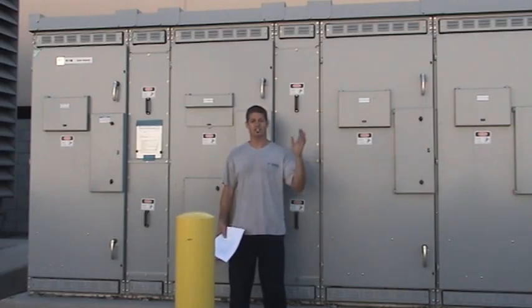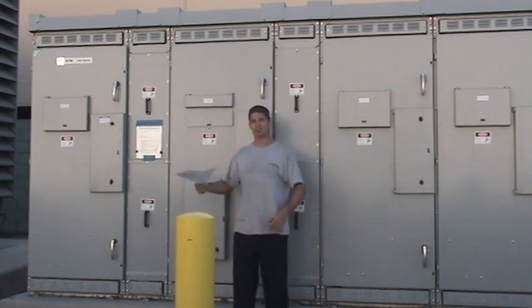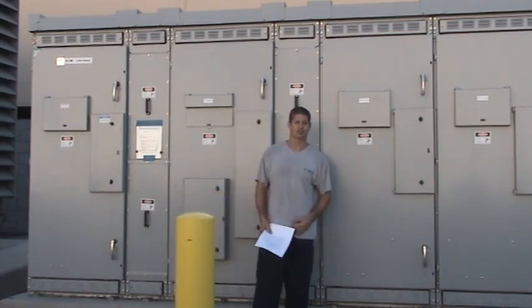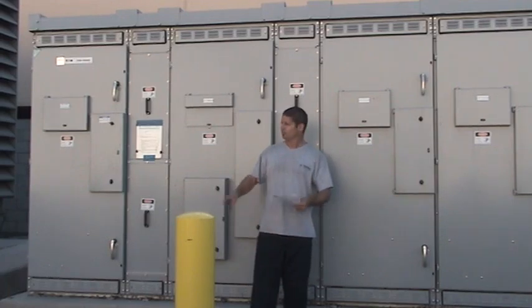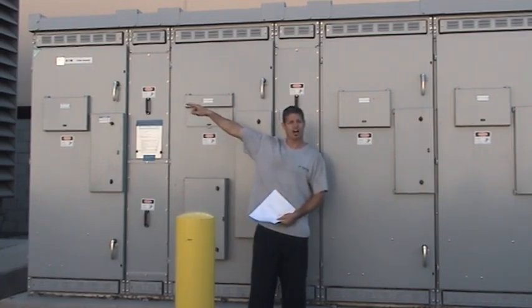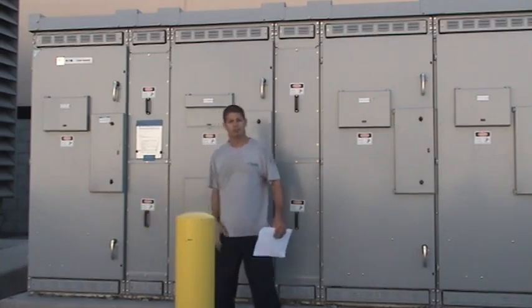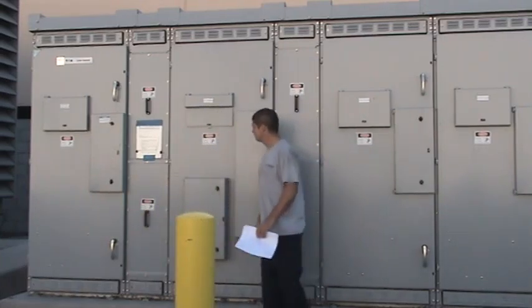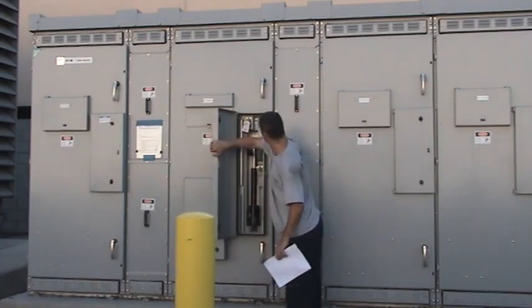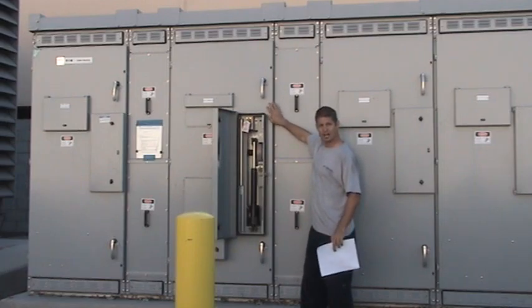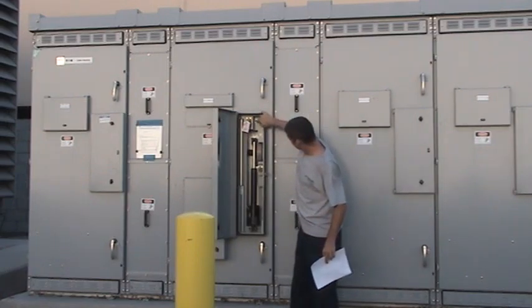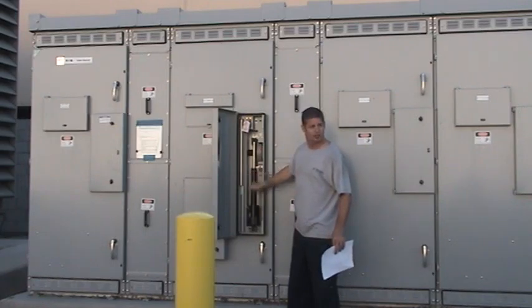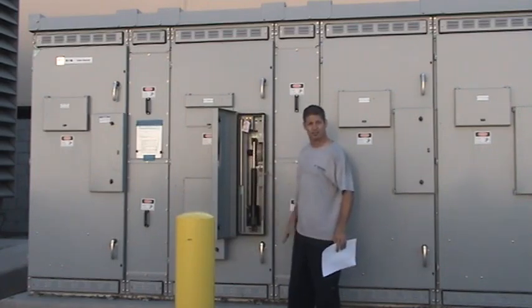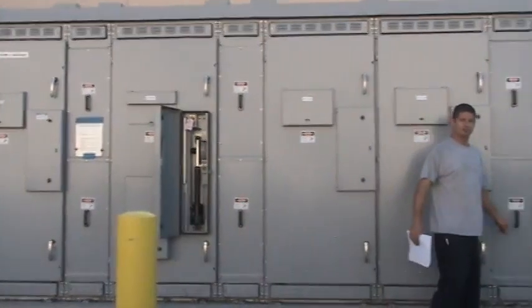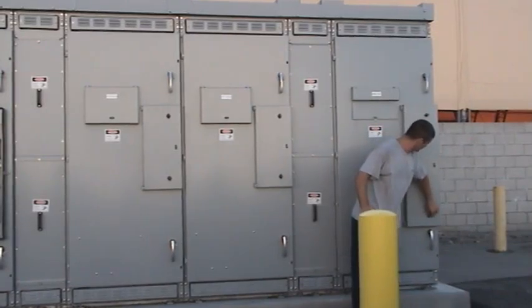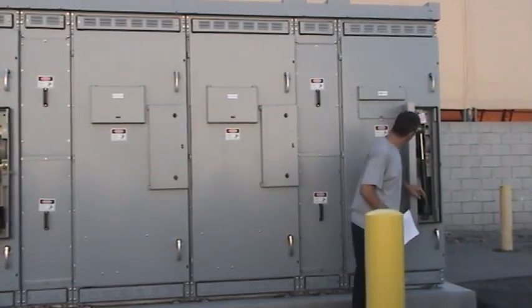That's because you need to know the whole series down the line before you can start opening and closing switches, right? So for manual operation, you would go down to MSV 13 where we had talked, and flip it into manual. From that point, you will have access to go into any of these. This is the tie switch for this gear, and you could flip the open/close, and it would activate the actuator, which would actually open and close your gear. The main is on right here, and the main has the same function. The mains and ties at both ends have the same function.